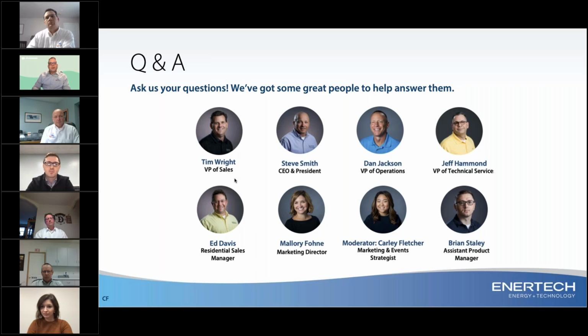Certainly, thanks, Brian. Yeah, it's a great question and a good reason to attend John Siegenthaler's seminars, because he'll get into that in a lot of detail. This heat pump is limited to 135 degree leaving water temperature. So we have a couple of choices. We could go with different emitters, with low temperature emitters, double stack baseboard or something to that effect, or some really nicely designed radiating devices, or we can go the backup boiler route. You can go either way, but the heat pump is limited to 135 degrees, and John will get into a lot of those details on his webinars coming up. We also have some drawings in the IOM that show boiler backup piping.